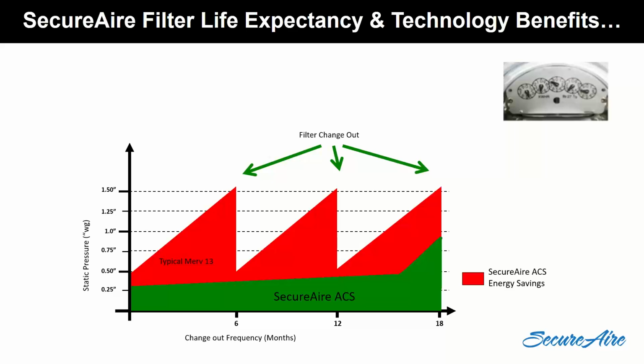But mine lasted basically on average a year. Whereas my old filter, I might have had it changed 3 times in 1 year. My old one was a Merv 10, no, Merv 11, I think it was. So my new filter has a higher Merv rating, but I change it less often. And sometimes that can be the case. Typically, the deeper the filter gets for a given Merv rating, the more space it can load stuff on. So the more pleats it has, if you will, the more space it can load stuff on, and hence the lower the pressure drop, and the longer the filter will last.